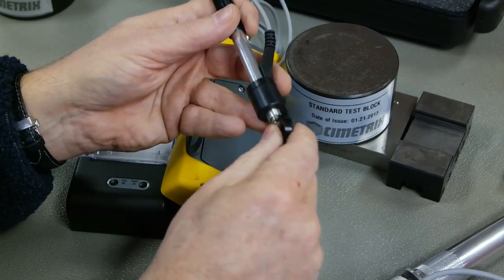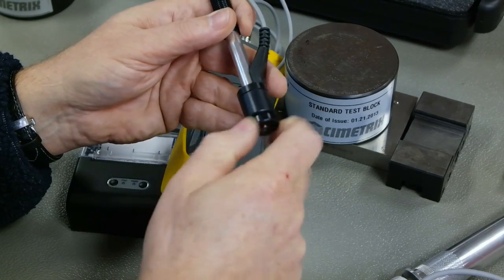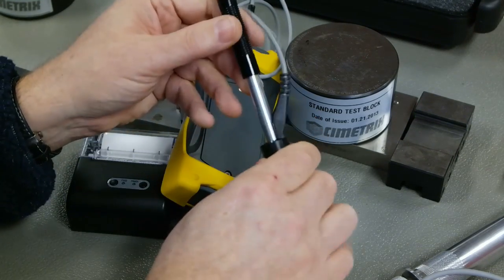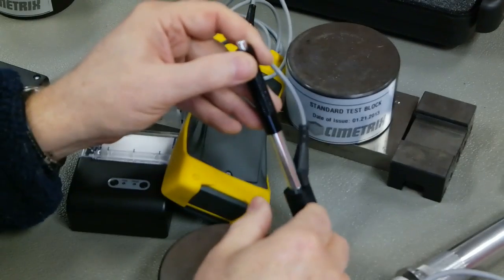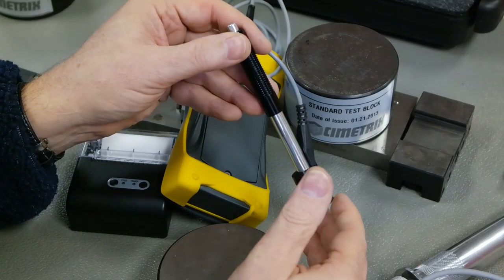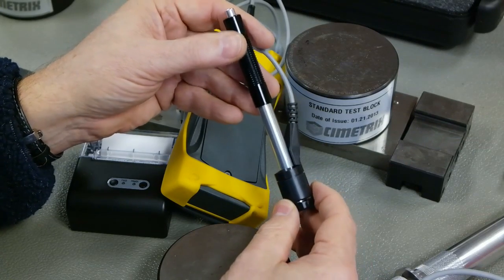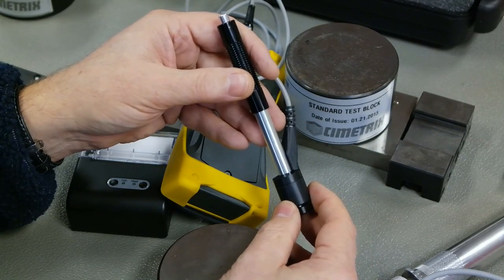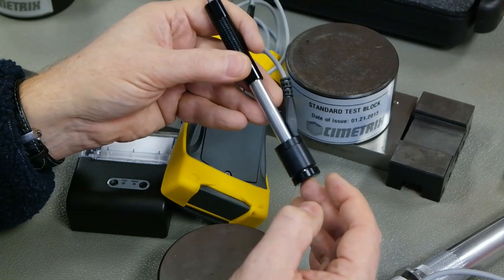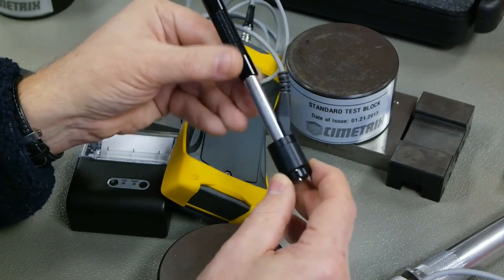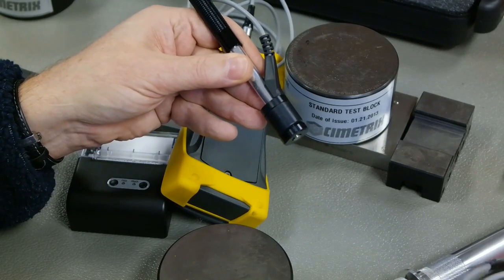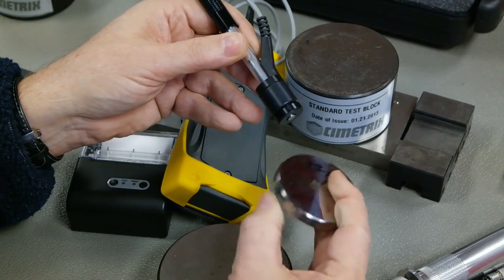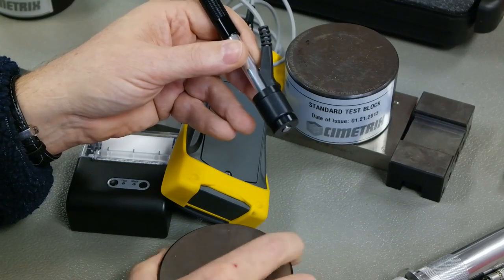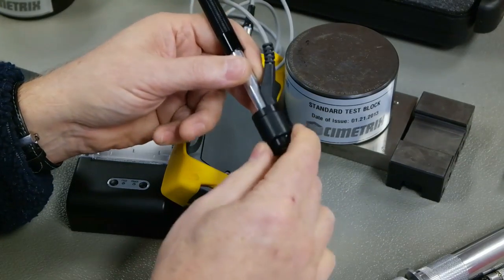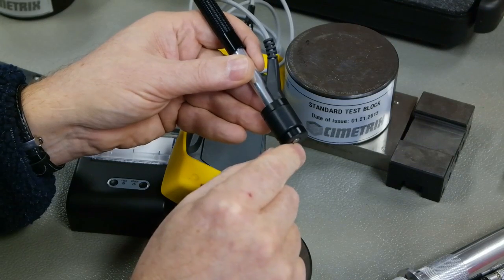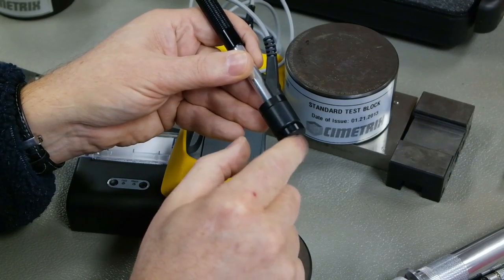Now the reason that we have these, in addition to the UCI, is that ultrasonic technology is great for ferrous materials that are of tight granular structure like steel, stainless steel and so on, but not much good for very soft materials, or certainly not for very grainy materials like cast iron. So you'd use this device when you were testing those sorts of materials. The thing is that these are not good for super thin parts, so parts thin like this, and the test block, in fact, the calibration block, is this great big guy. This requires thicker parts because of the technology, firing that little slug against it. It can't have a thin part because it'll just absorb the impact.